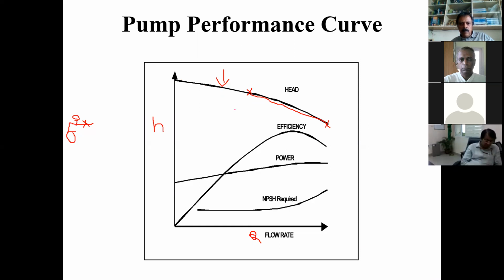The head here basically refers to the system resistance. So what is the system resistance? This pipe is going to a set of heat exchangers here. So maybe this is a system. You have some heat exchangers, and water is going to a cooling tower, maybe. So you have a cooling tower like this, and the cold water is coming back to the pump. So this is the system. What is the resistance offered by these pipes, the heat exchangers here, and the vertical lift that is going to take place in the cooling tower? All this determines the pressure, or the head, against which the pump is going to work. So the higher the head, the higher the resistance, the lower will be the flow rate. You can see here the head goes up and the flow rate comes down.